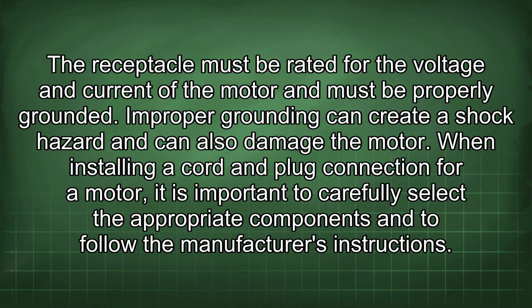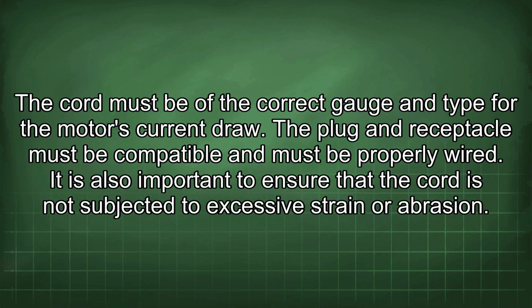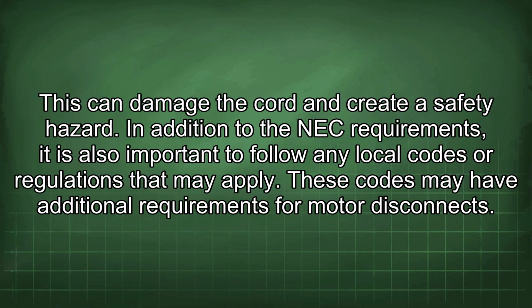When installing a cord and plug connection for a motor, it is important to carefully select the appropriate components and to follow the manufacturer's instructions. The cord must be of the correct gauge and type for the motor's current draw. The plug and receptacle must be compatible and must be properly wired. It is also important to ensure that the cord is not subjected to excessive strain or abrasion. This can damage the cord and create a safety hazard. In addition to the NEC requirements, it is also important to follow any local codes or regulations that may apply. These codes may have additional requirements for motor disconnects.